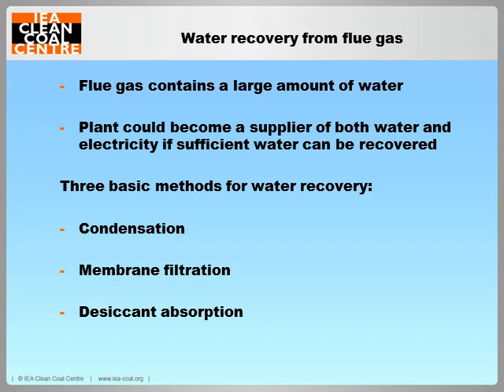no FGD unit. If enough water could be economically recovered from the flue gas, then a dry-cooled power plant could become self-sufficient in water, or in some cases could possibly become a supplier of both electricity and water. It is unlikely that enough water could be recovered to supply the cooling water make-up requirements for a wet-cooled power plant.